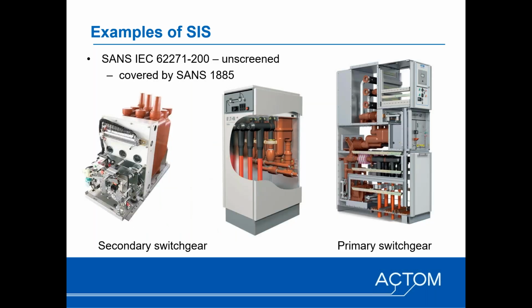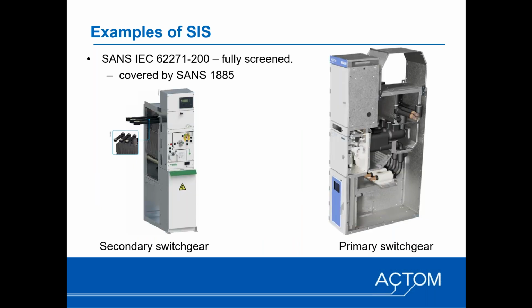Here are some examples of solid dielectric switchgear under -200, which is metal enclosed, which would effectively be covered by SANS 1885. And you can see their typical metal enclosures as we would be familiar with, but fixed pattern, and you can see the epoxy resin insulation embedding all the primary conductors. What we see here are all examples of unscreened solid dielectric switchgear.